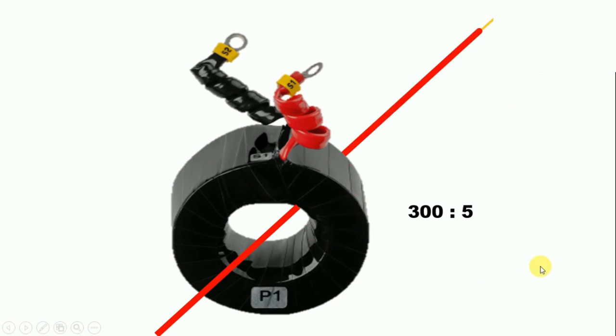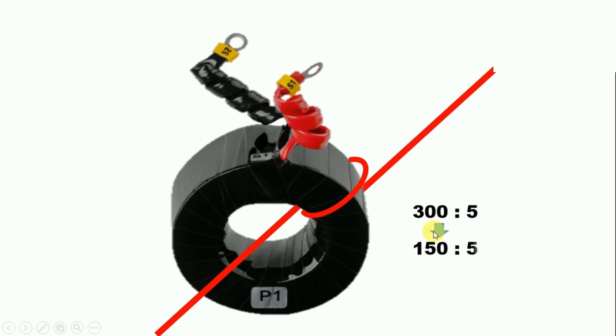Now suppose the ratio of our CT is 300 by 5. If we make one turn of wire, the CT ratio will become 150 by 5. Note one thing: when the ratio changes, only the primary side changes. The ratio of only the primary winding changes, because we are modifying only the primary winding. The secondary winding ratio remains the same.